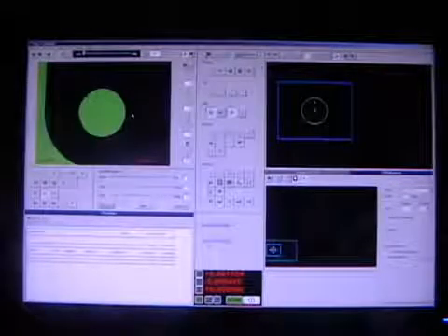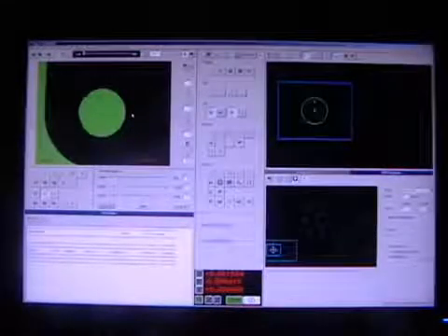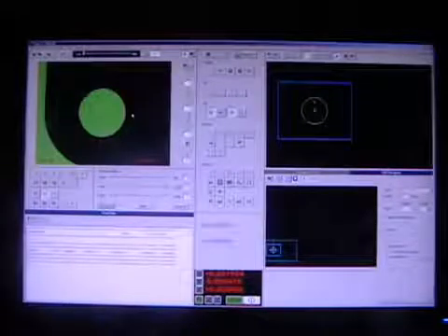Also, as we go over here, let's bring your eyes over to the live field of view image. As the destination triangle comes into the field of view, we can see that the destination is highlighted here in the field of view as a circle, and where we're currently located is highlighted as a blue plus sign. And what the system is guiding us to do is overlay the blue plus sign into the circle, and when it does, it happened quickly, but it fired off the edge detector, the feature finder target, and it measured that circle.